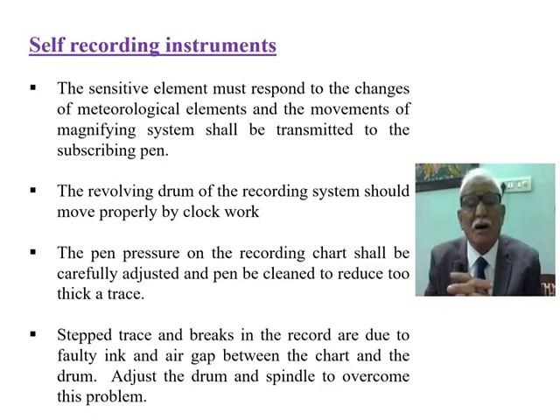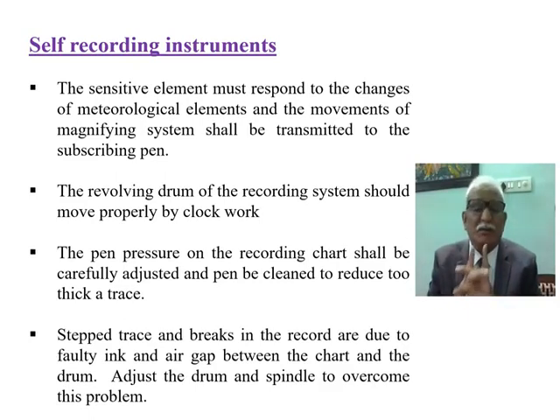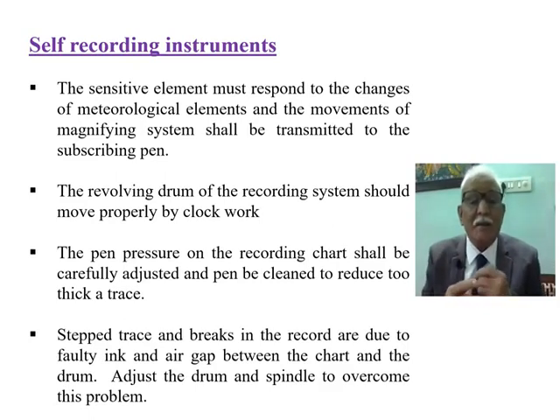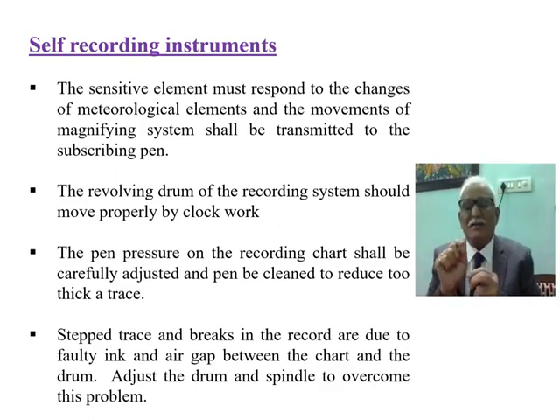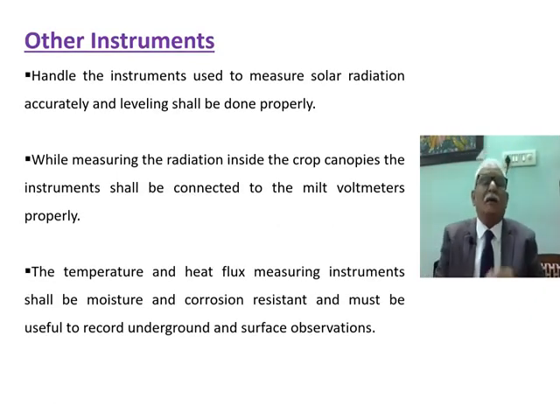The revolving drum of the recording system should move properly by clockwork — in 24 hours, it should record the rise and fall of temperature, humidity, and pressure. The pen pressure on the recording chart should be carefully adjusted and the pen cleaned to produce a neat, single-line trace of minimum width but 100% visible. Also regularly check for any breaks in the recorder trace.